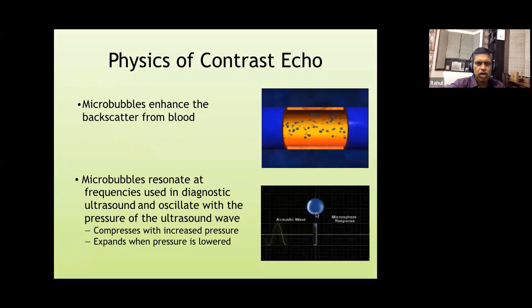This happens because of the microbubbles, which are designed in such a way that they are able to backscatter ultrasound waves, and they end up resonating when we transmit an ultrasound wave of a particular frequency. The microbubbles resonate at frequencies that are used in these ultrasound machines, and they oscillate with the pressure of the ultrasound wave. They compress and then they expand when the pressure is lowered. Based on this, they generate acoustic waves, and because of this, we get a much more prominent reflected ultrasound wave. Unlike the blood pool, which is usually black, a blood pool loaded with contrast appears very prominent, very much white.